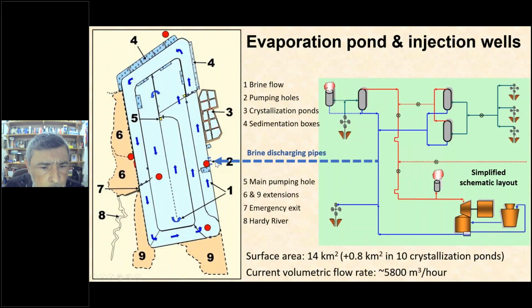The brine reaches this point, where there are a couple of pumping holes, and from there it is pumped inside the evaporation pond in this spiral trajectory up to this point, which is the main pumping hole, from where it is sent to the injection wells that are marked here in red circles. During this trajectory, the brine reduces its temperature, of course, and deposits some minerals in its composition, particularly silica, SiO2, and eventually is returned to the reservoir.